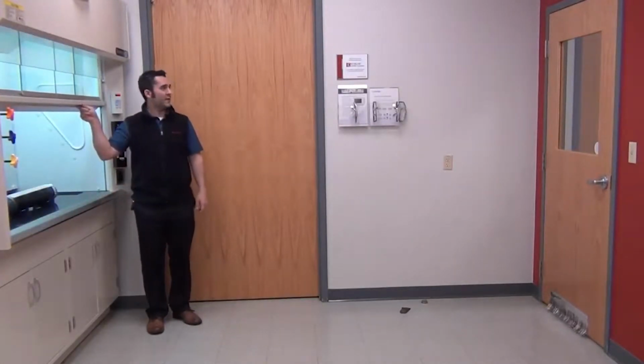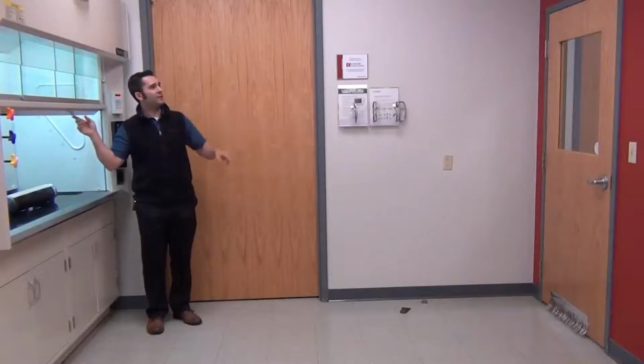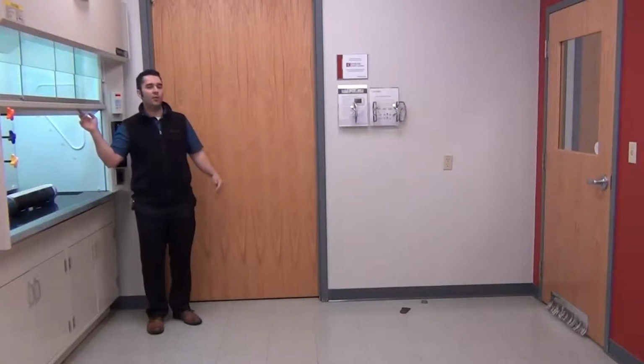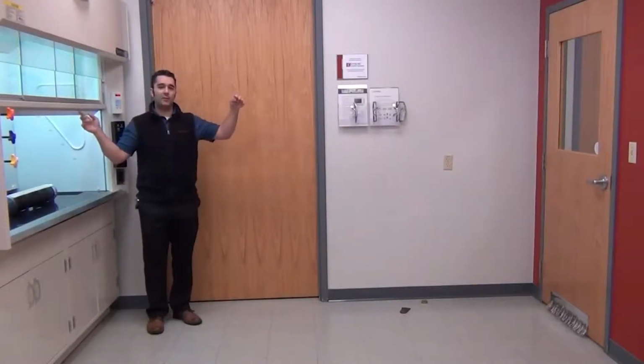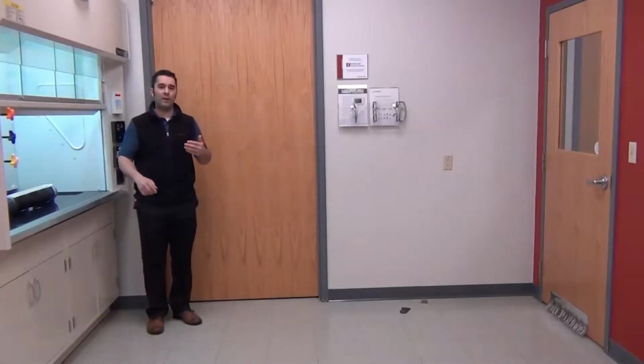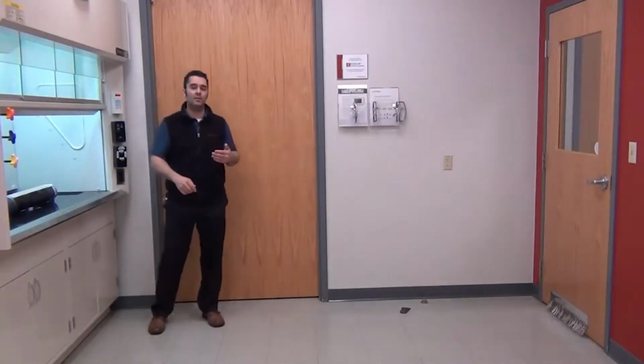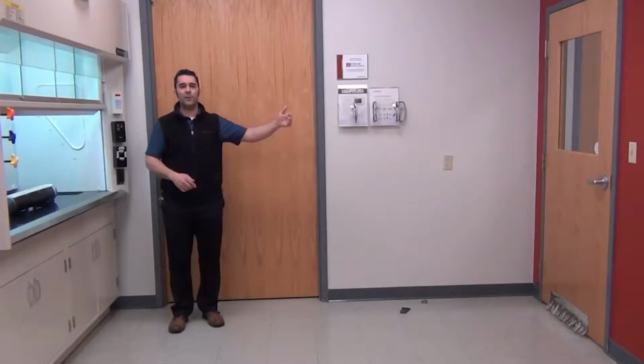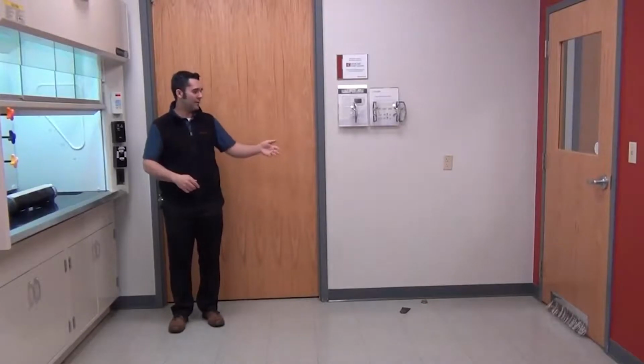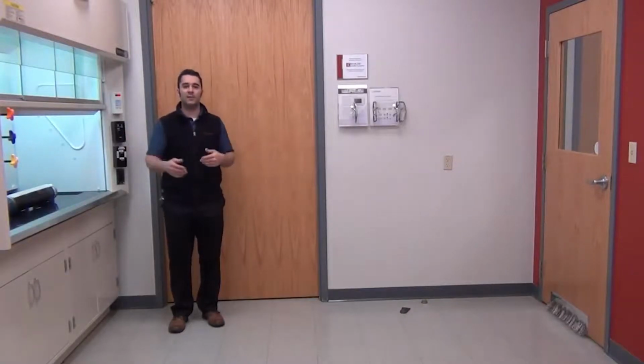As I open my sash, my pressure just spiked to 0.1, 0.12, 0.08, 0.07, 0.06. So not only did my pressure spike, meaning I'm pulling way more air into this space than I need to, that also means that my adjacent spaces, my corridor and any rooms on the other side of the hallway, their pressurization is also being affected. But I settled out roughly where I was before, 0.025, 0.022, something like that. But it took 15 seconds to get there.